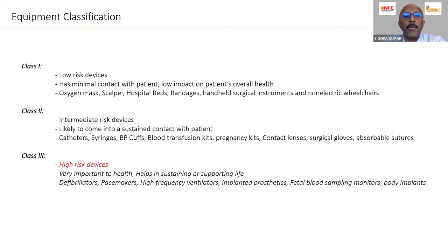These are equipment operating with very low voltage. That means even in case of a fault, the operating voltage is not enough to create a shock to a normal person. We should understand it, a normal person. For example, in a wet area, the shock voltage is something about 25 volts. Class 3 equipment probably works at a lesser voltage. So it may not create a shock directly to a doctor or a medical professional. But for sure it is a risk for the patient, because once the skin is bypassed, even a very low voltage could create a problem.